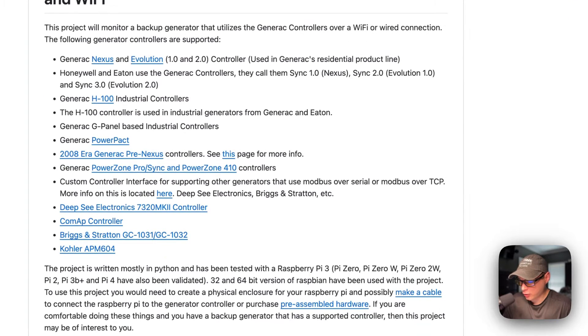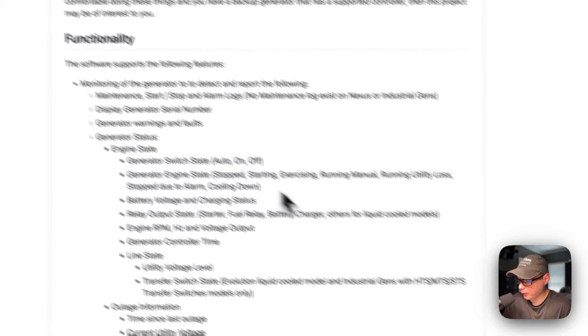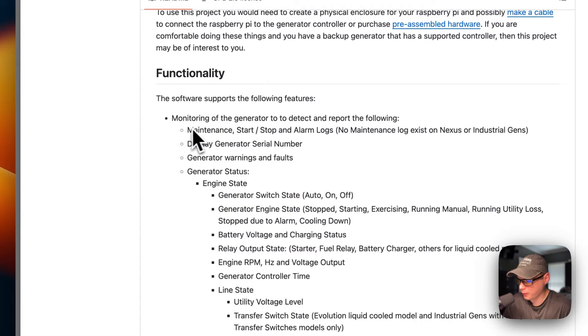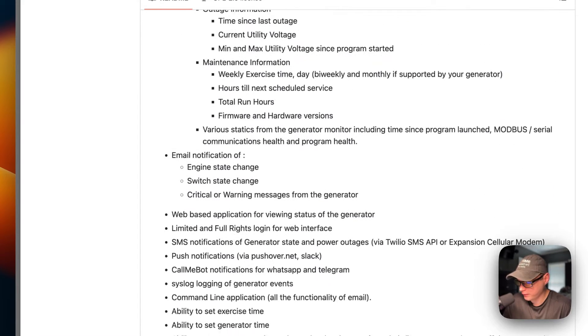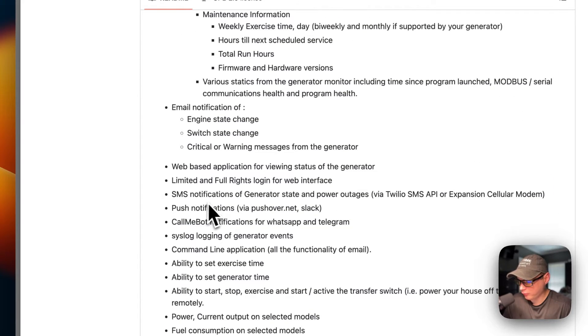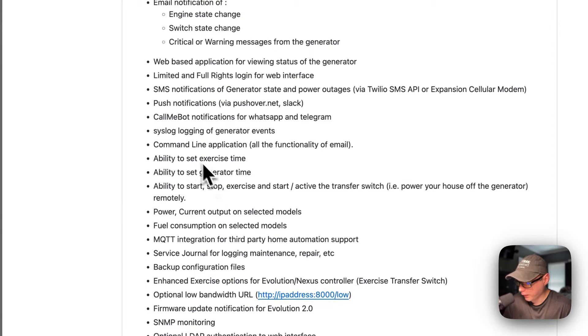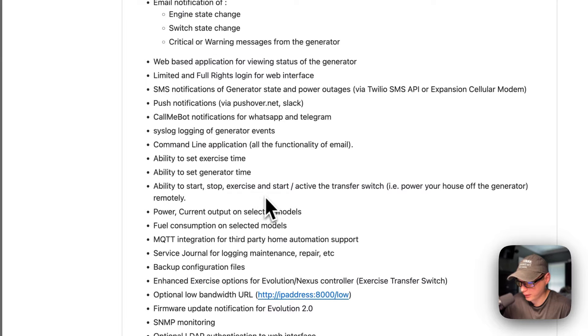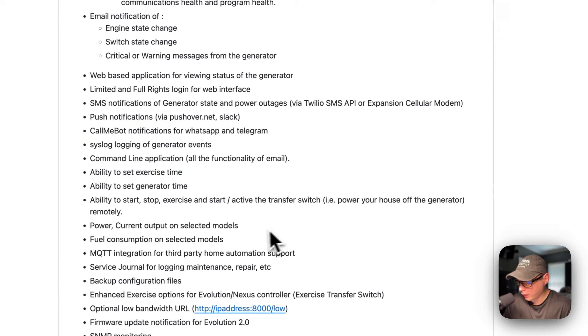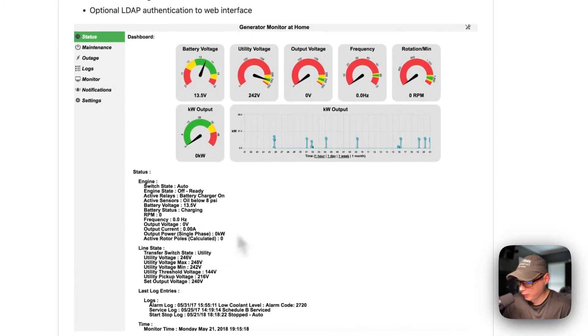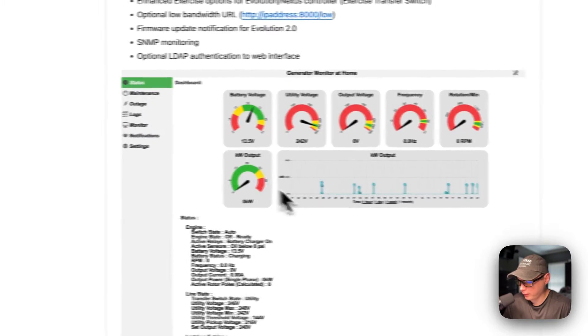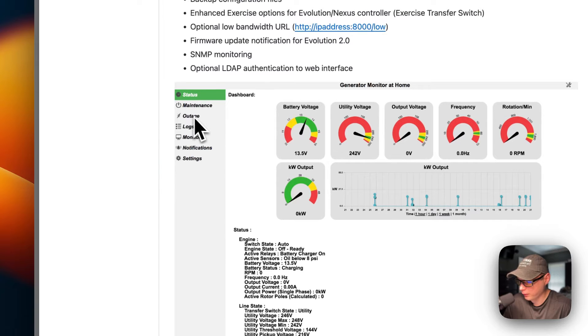The functionality includes monitoring a generator and displaying serial numbers. You can get SMS notifications and email notifications, and you can also use CallMeBot. The command-line application has full email functionality, the ability to set exercise time and generator time, and the ability to start, stop, exercise, and start an active transfer switch. The UI shows status, maintenance, outage logs, monitor, notifications, and settings.